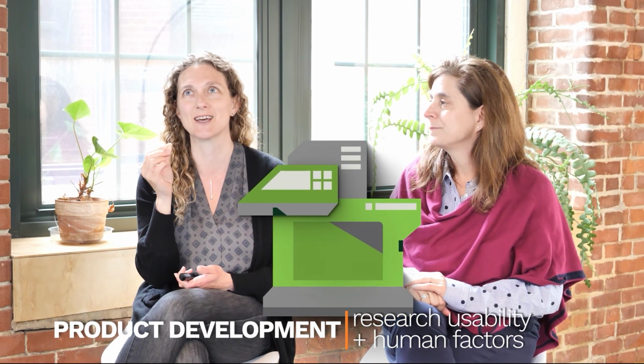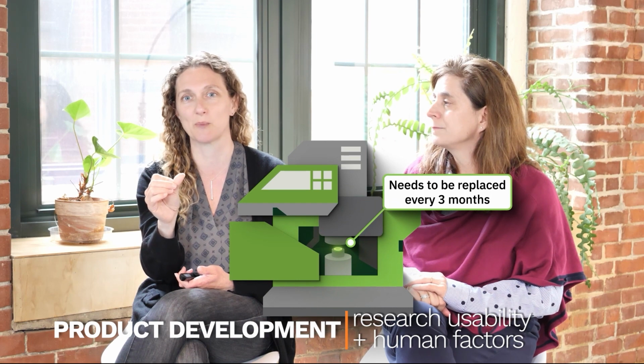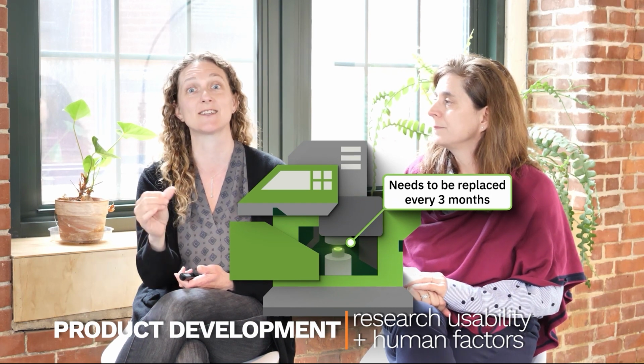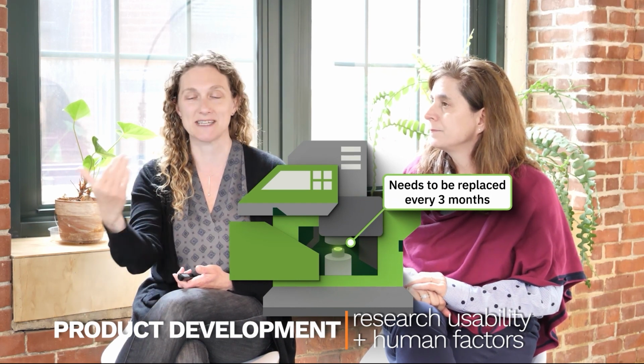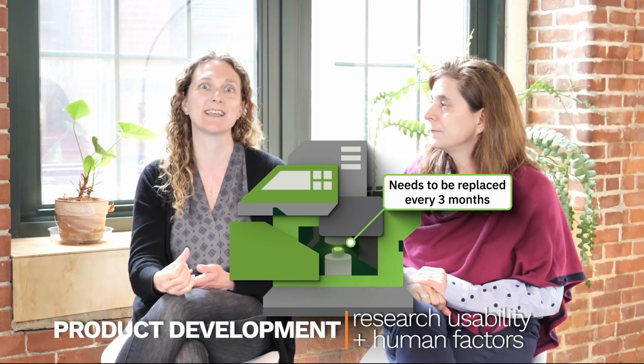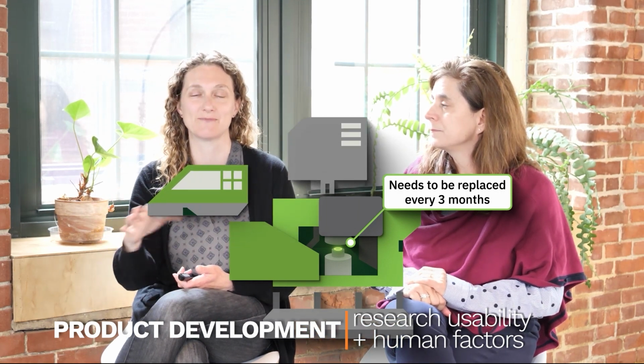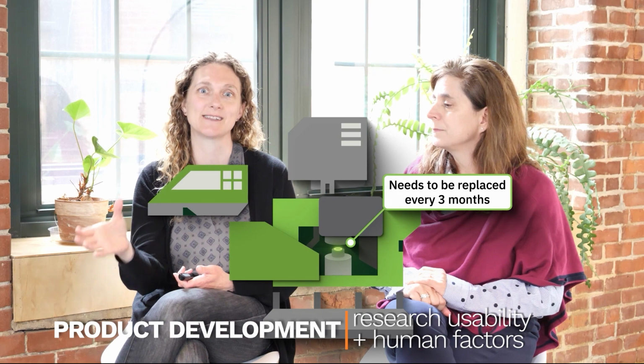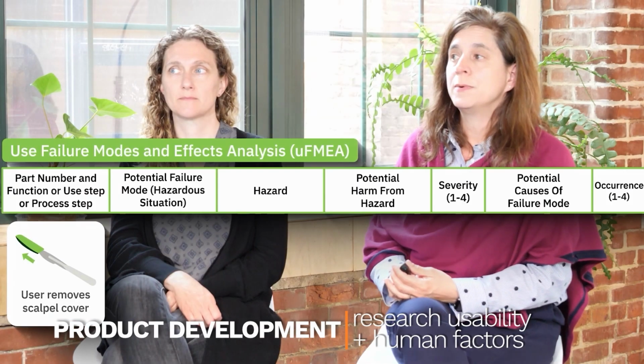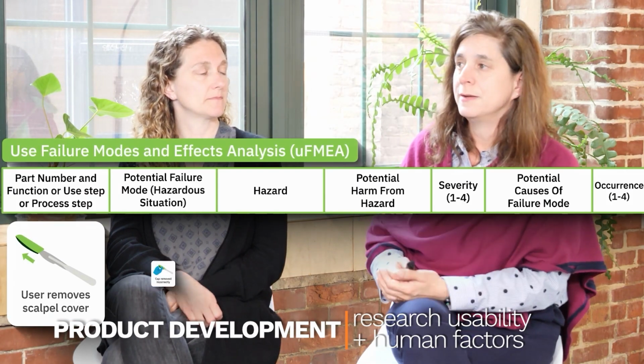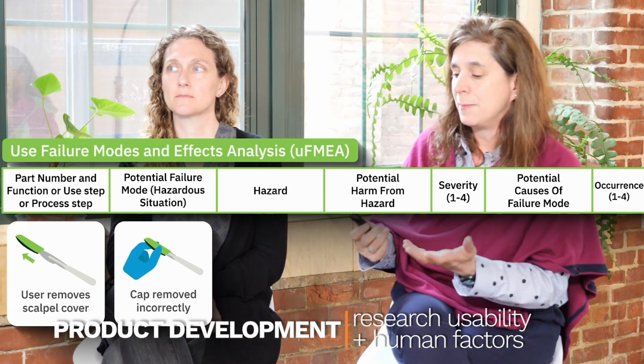I have heard stories of devices where the fact that a little O-ring needed to be replaced every 3 months wasn't taken into account in the design. And so when the technician needed to come in and replace that, the entire device had to be taken off the floor.